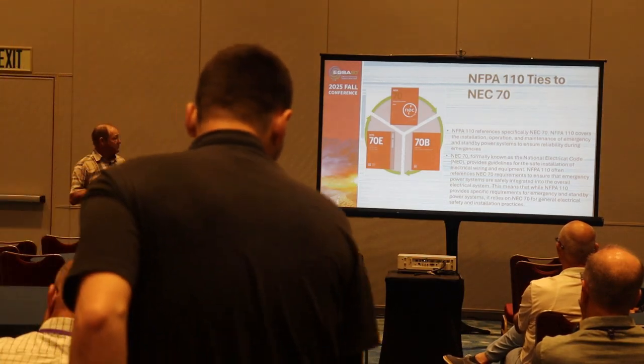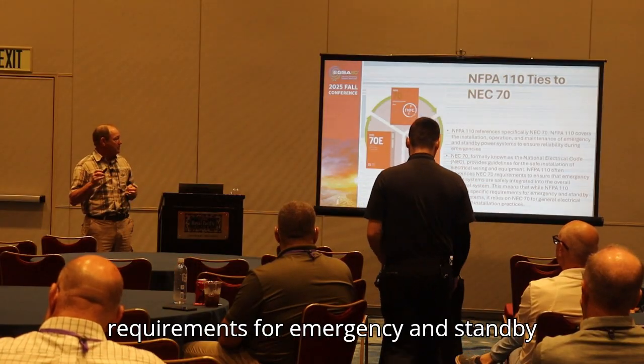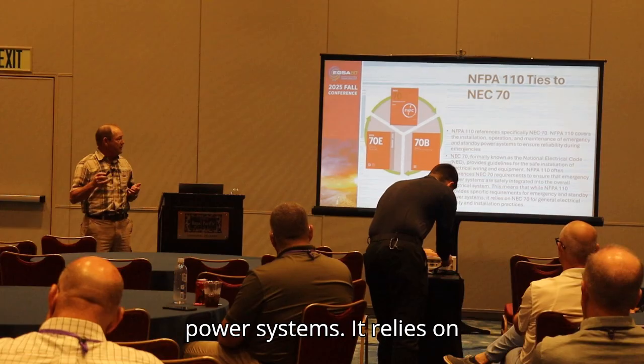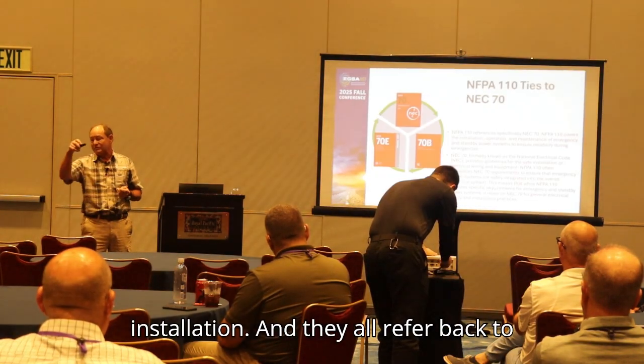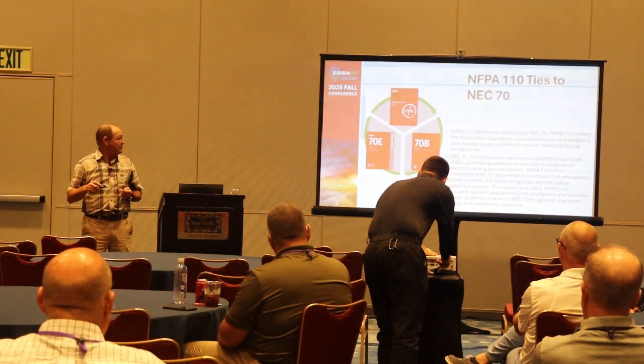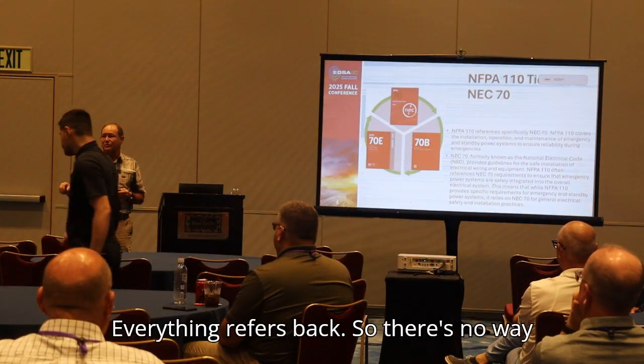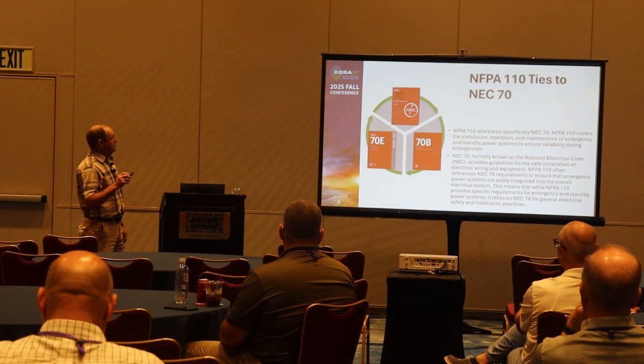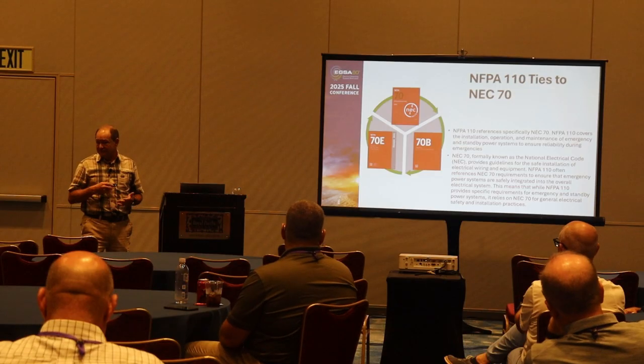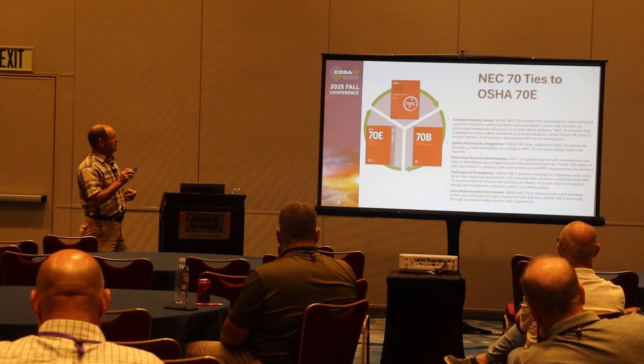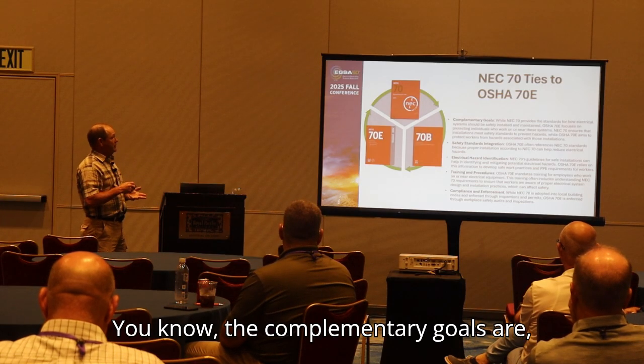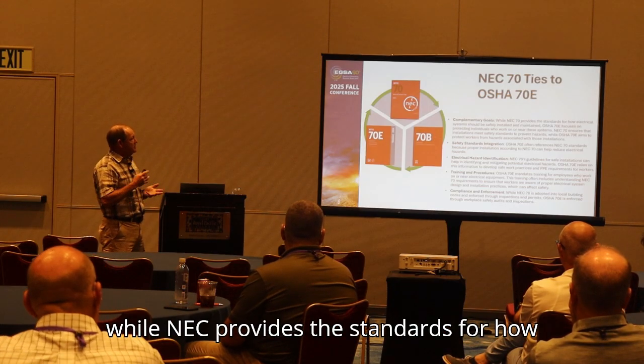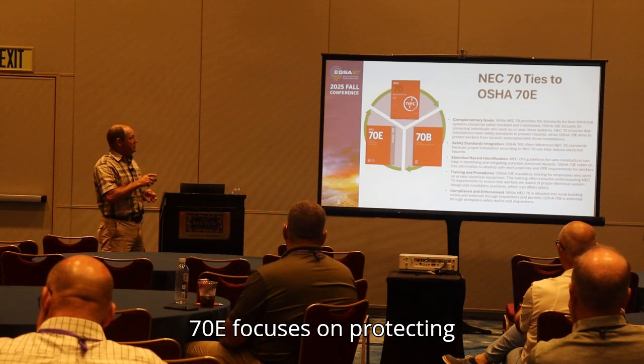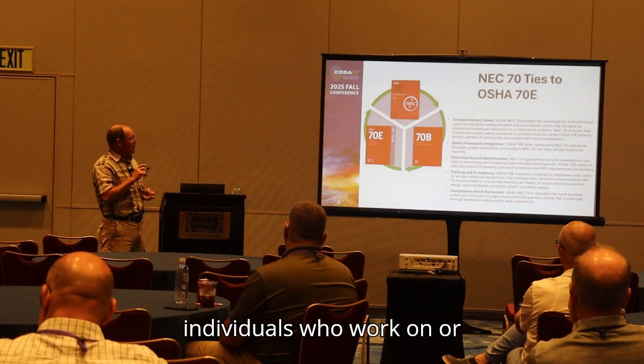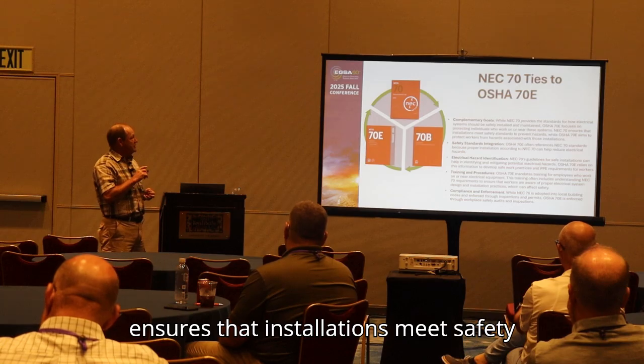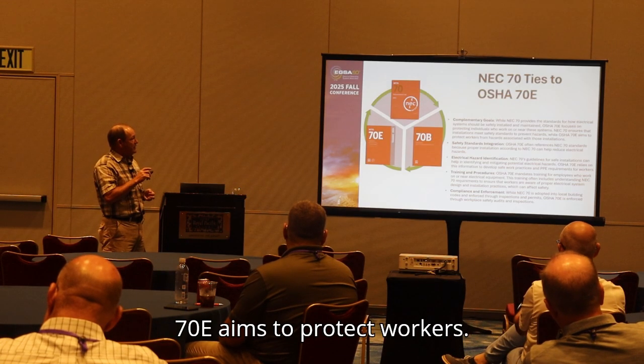NFPA 110 provides specific requirements for emergency and standby power systems. It relies on NEC for general electrical safety and installation, and they all refer back to 70B and 70E. So that loop is there - everything refers back, so there's no way to get around this. 110 ties to the National Electric Code, and NEC 70 ties to OSHA. The complementary goals are: while NEC provides standards for how electrical systems should be installed and maintained, OSHA 70E focuses on protecting individuals who work on or near these systems. It ensures installations meet safety standards to prevent hazards, while OSHA 70E aims to protect workers.